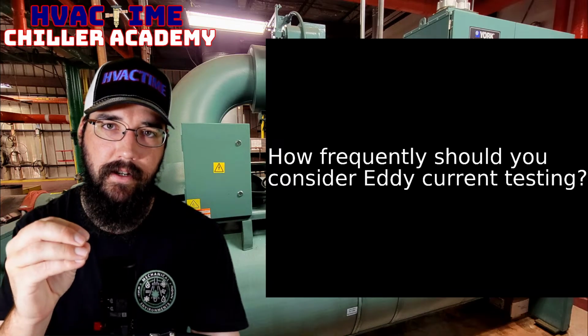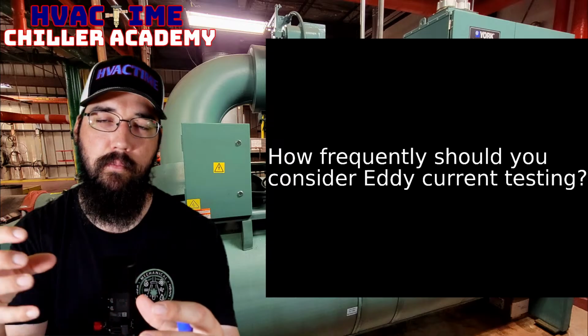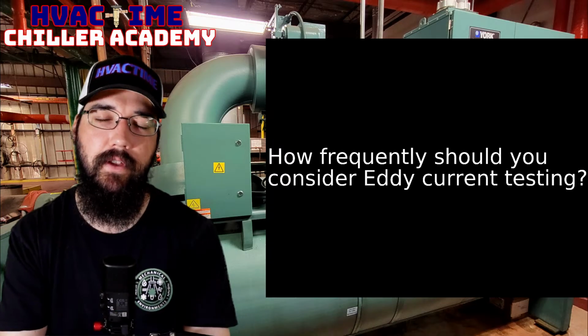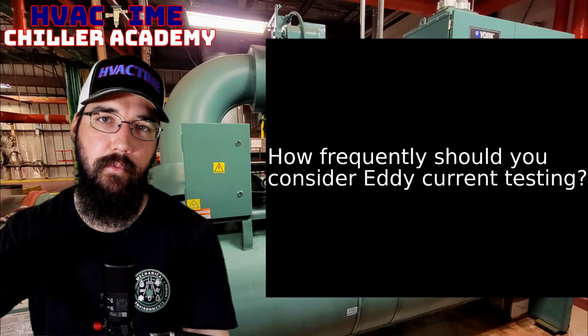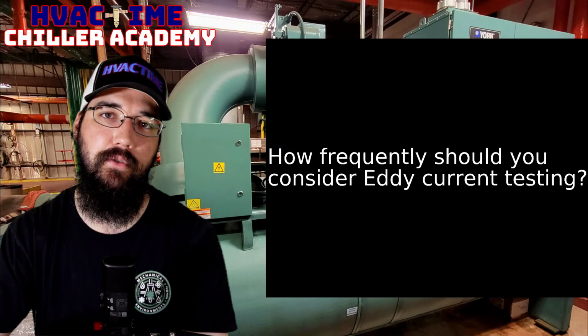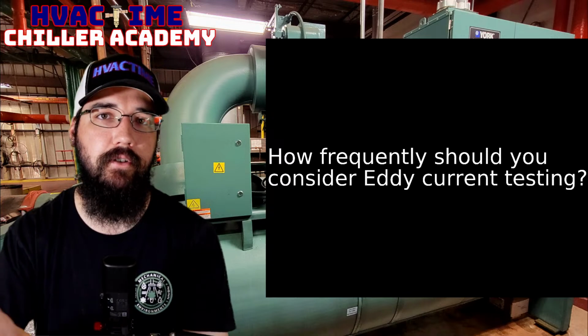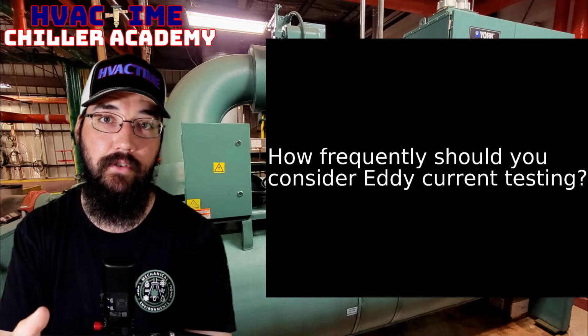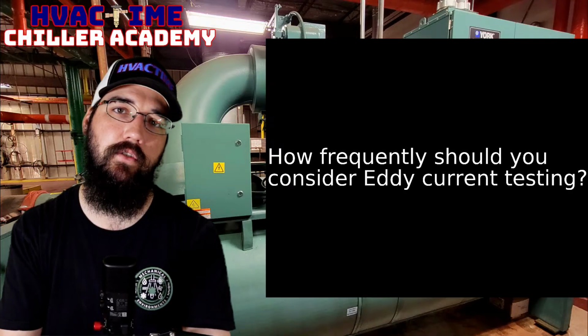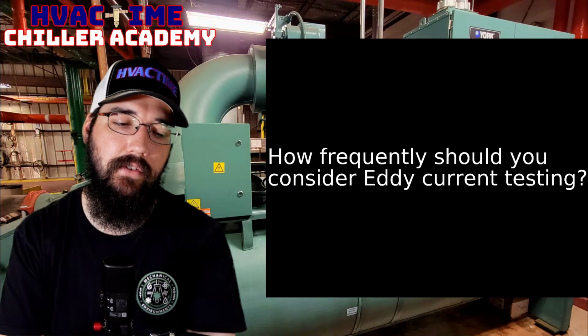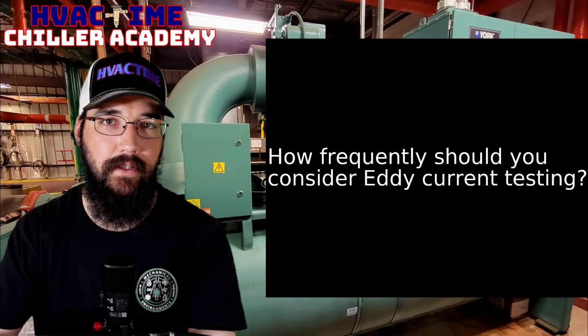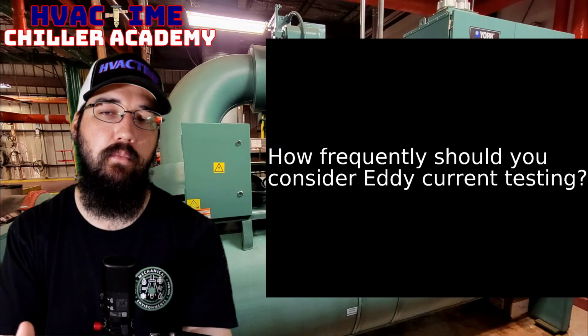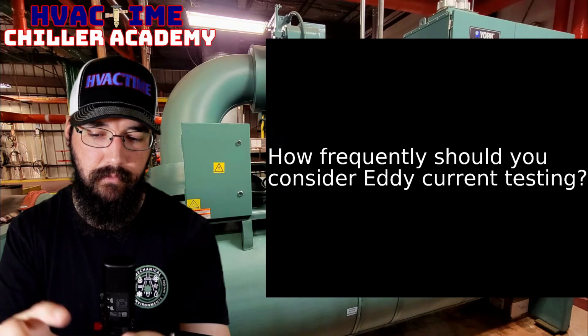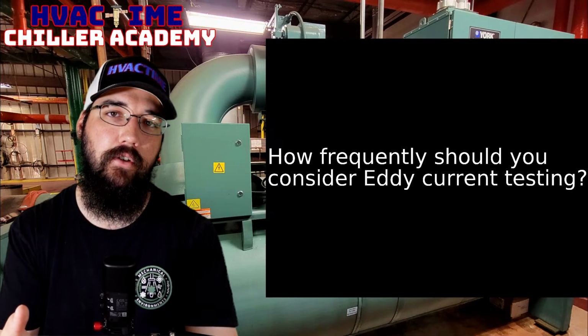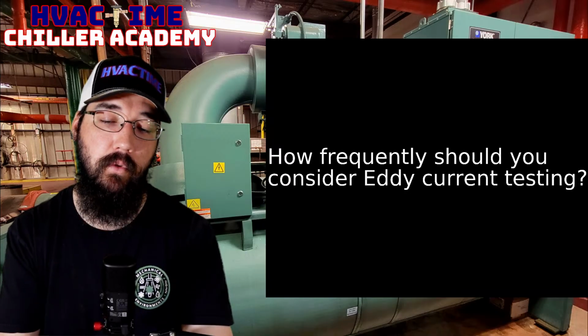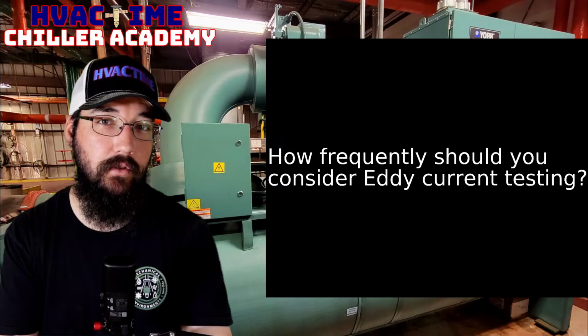The eddy current itself is a little probe that sends out an electromagnetic field, and there's an oscilloscope-type device monitoring that field for variation or interruptions. An eddy current certified technician monitors that as they go down each tube, and when they see certain disruption patterns in the field, that can indicate either a bulge, depending on the shape of the pattern, or an actual hole. The ones I've worked with have been able to tell the difference between the two.